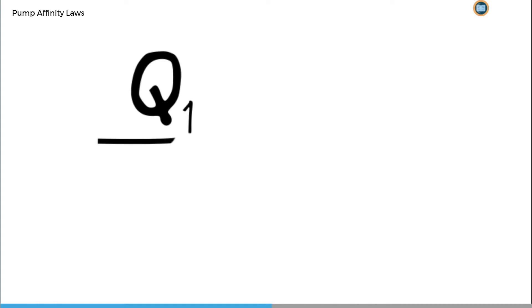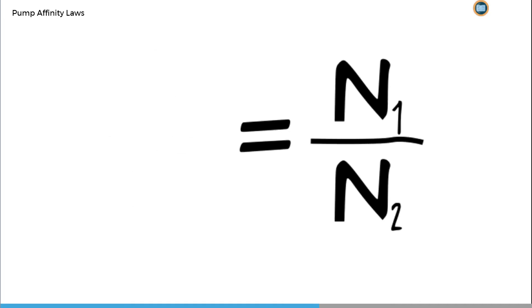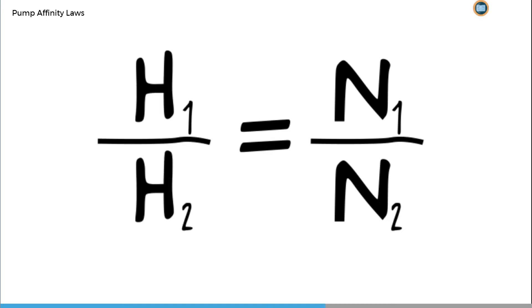This means that for a particular pump, the ratio between two volumetric flow rates, Q1 and Q2, is equal to the ratio of their respective rotational speeds, N1 and N2. Similarly, the ratio between any two values of head developed, H1 and H2, is equal to the ratio of their respective rotational speeds, N1 and N2, squared.